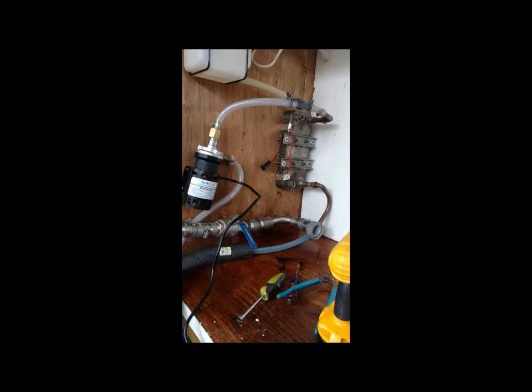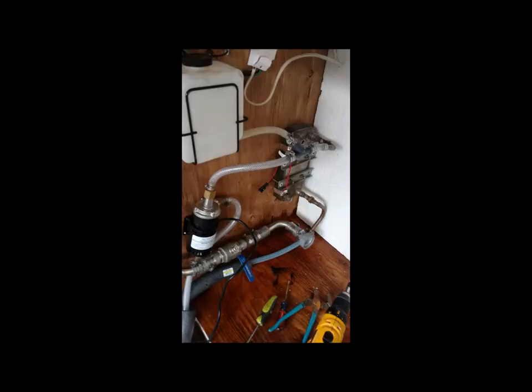Onto the heat exchanger, I had an issue with air bubbles in the flow lines, so I repositioned the heat exchanger lower, mounted the pump at an angle, and placed an overflow reservoir at the highest point of the coolant loop. This resolved the bubble issue.